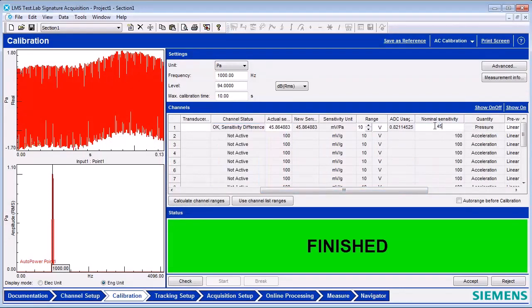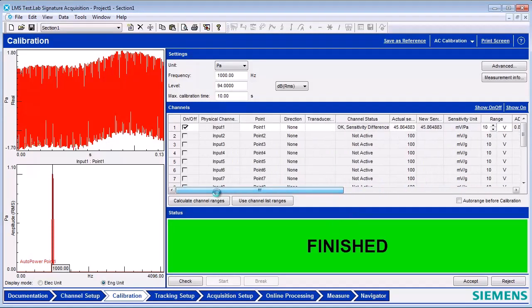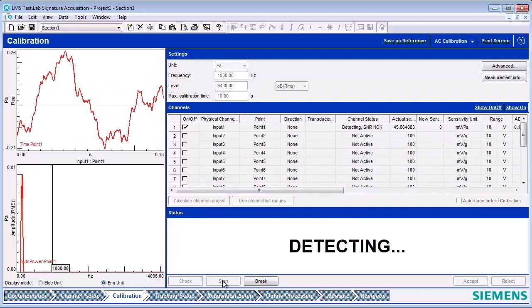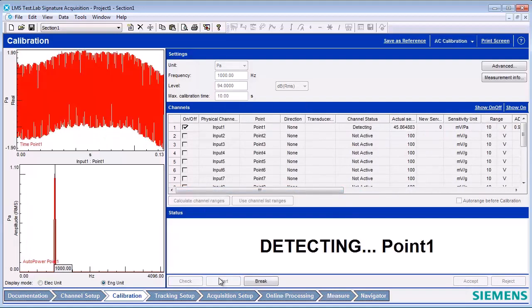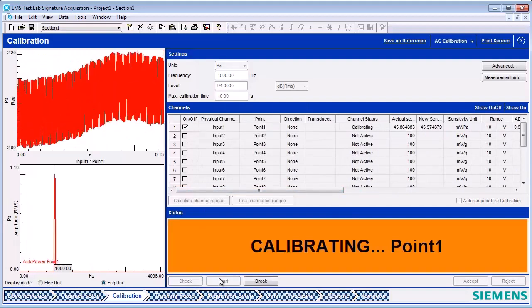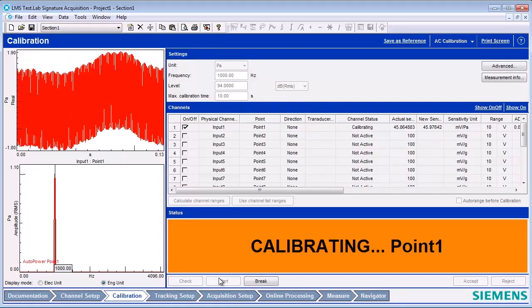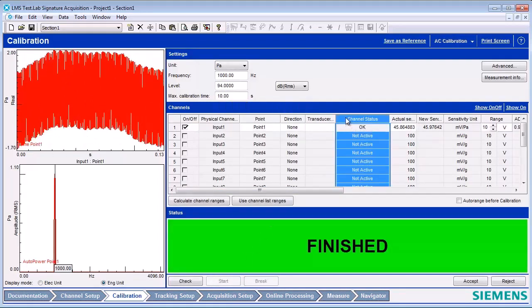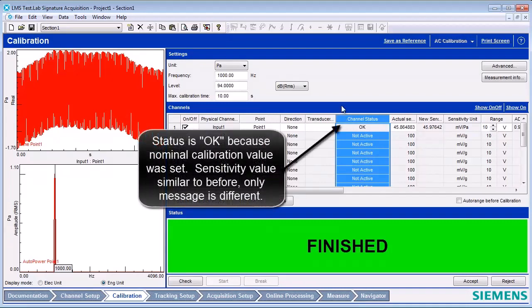Performing the calibration again results in a different channel status. Here you can see that the channel status is now OK and there is no sensitivity difference message. This concludes the calibration of a single microphone.